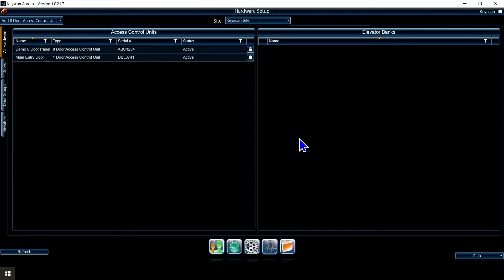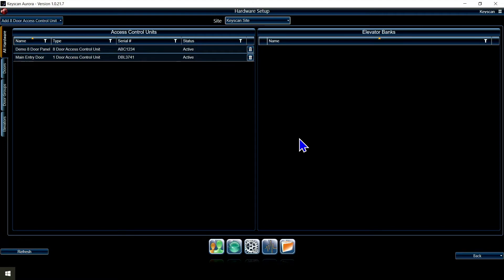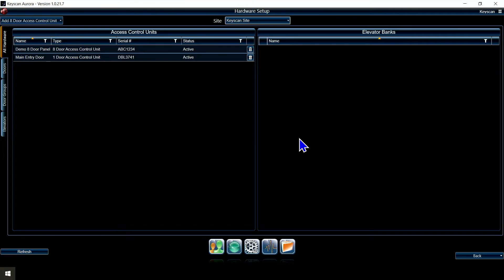Once you do that, one final note on your panel setup: do the hard reset that is recommended in the setup guides. The panels are tested at the factory. We take every panel that's made, put it on the wall, test it for 24 hours to make sure we don't have any issues. That's why every panel we send out works when it gets to the site. So there is a little bit of a program in there already. We want to get that out. We want to make sure you blow that out before putting it on your system, just so you don't have any kind of data corruption issues or anything.